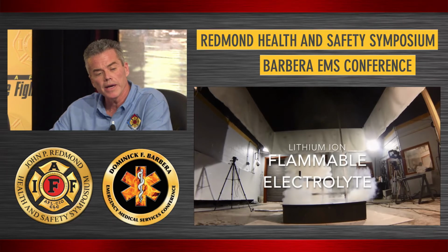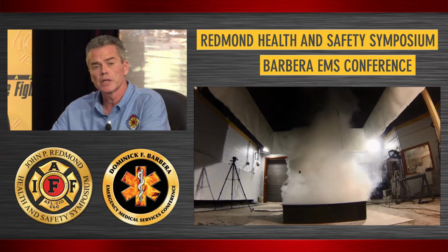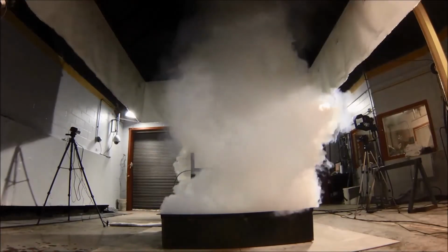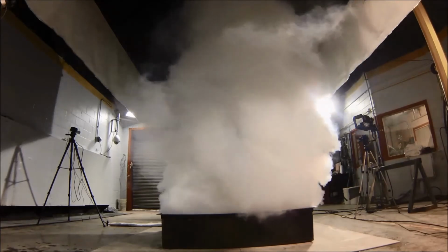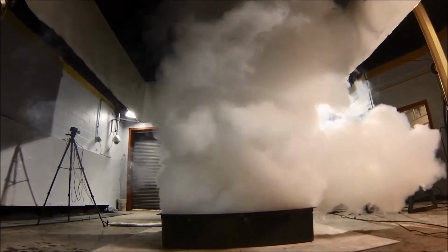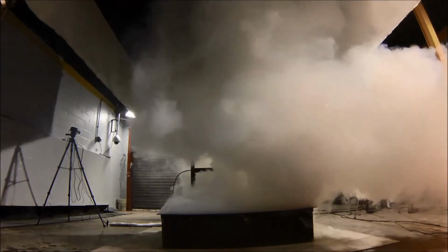There's not that much data out there, and we're collecting it now, but what we're finding is that when these things do go up, there are some toxic, corrosive, and flammable gases. As you can see, that white smoke - you saw that in Sean's earlier example - is indicative of this thing called thermal runaway. But that smoke right there is a flammable cocktail.